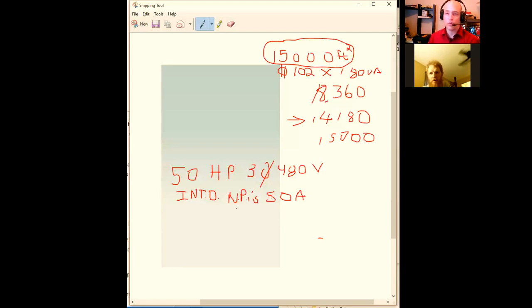And so if you look under 430.22(E) on page 329. 22 is your regular continuous duty motors. And then on the right-hand side of page 329, you'll see the table, which is labeled E. Look at the heading of that table. 5 minute, 15. No, that's the top, the label of it. I think it says nameplate. Yeah, it says nameplate rating, nameplate rating.